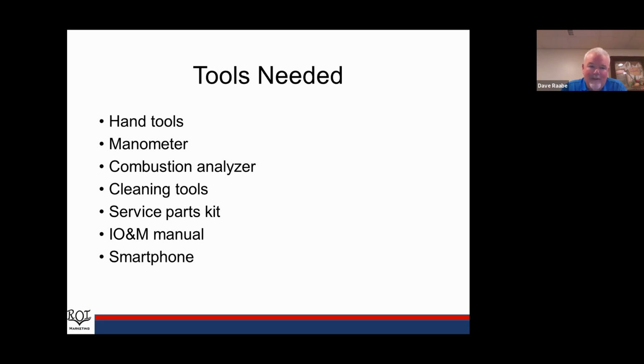I've heard guys say they can set up boilers. They can look at the flame by eye. You cannot do that on condensing gas boilers. You must have a combustion analyzer. So my advice to contractors is beg, borrow, or steal, but you need to have a combustion analyzer. That is your window into what's going on with that boiler. I would recommend taking cleaning tools with you if you're going out on a condensing boiler.